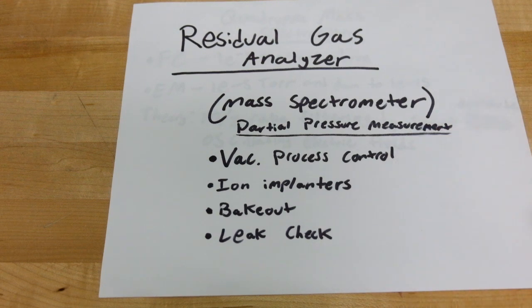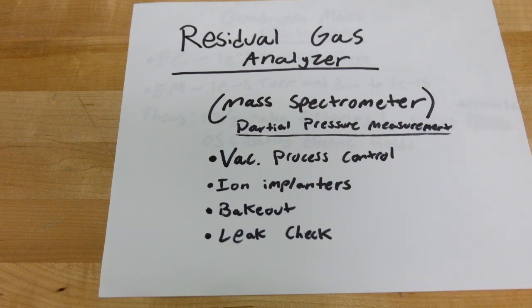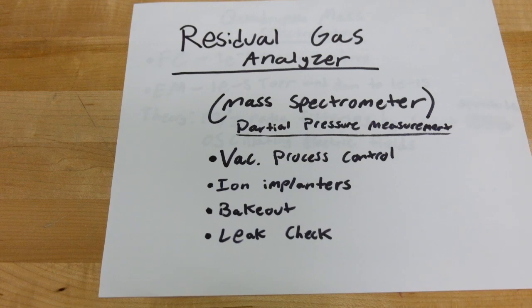That's extremely useful for all vacuum process control applications. For doing a bakeout, you can see how much water vapor you have left in the chamber. For leak checking, you can see the different hydrocarbon compositions. So if you have oil backstreaming from your pump, that'll be really easy to see on the RGA. It's really good for knowing if you need to put a cold trap or something like that. It's a really useful tool, and you can also do some other experiments — I'm going to be trying some stuff soon with heating up different plastics in vacuum and looking at their decomposition on the RGA to try to identify them.